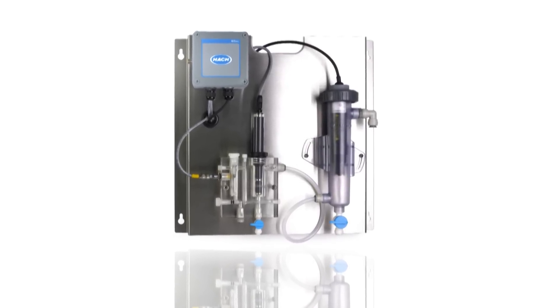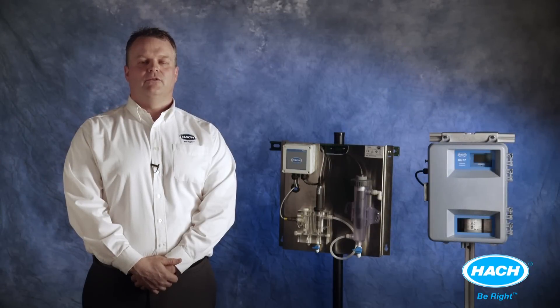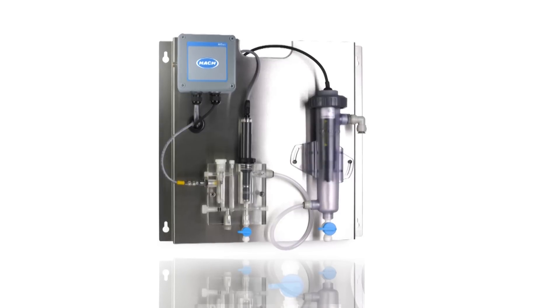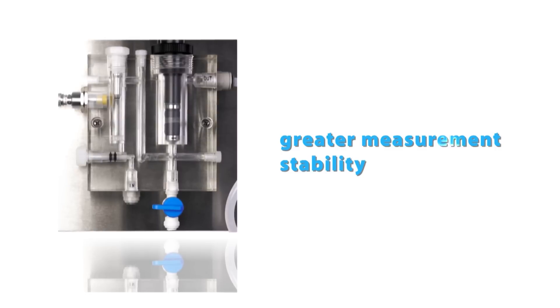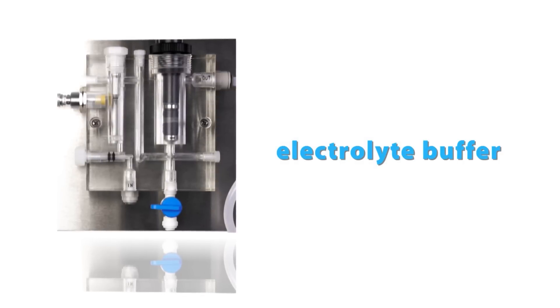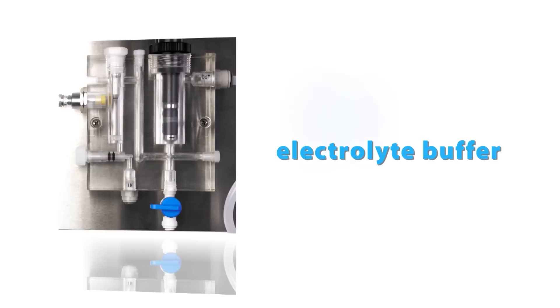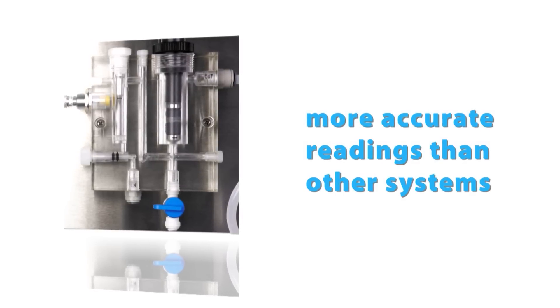Amperometric chlorine analyzers were approved for online analysis of chlorine under US EPA method 334.0 in 2009 after release of the groundwater rule. Unlike many amperometric systems on the market, the CL10 contains a three-electrode sensor which provides greater measurement stability. This instrument also uses electrolyte buffer to convert all chlorine species to a form detectable by the sensor, which gives a much more accurate reading than other systems using simple mathematical pH correction.